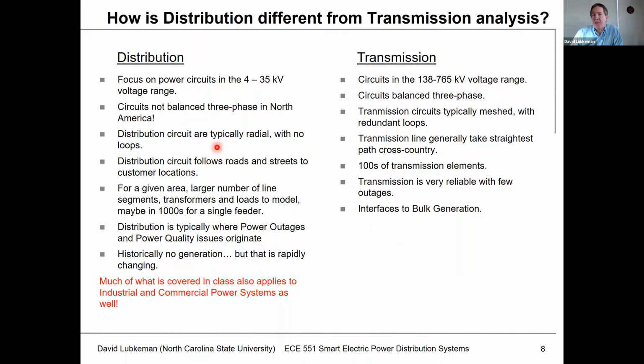We typically operate distribution circuits radially. We don't create loops, because that causes problems with voltage control and protection. It's like an upside-down tree—the branches go out, but the branches don't touch.